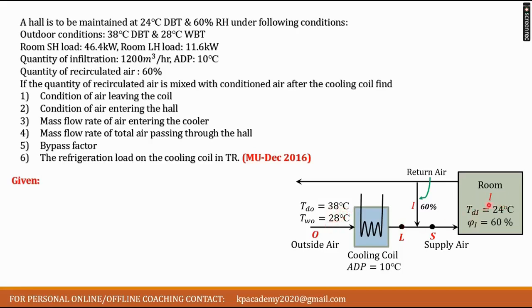Through some means we have room sensible heat and room latent heat given, that is 46.4 kilowatt and 11.6 kilowatt. But there is another thing that is given, the air infiltration. Through some means we have some air infiltrated into the room. The rate of that is 1200 meter cube per hour. We have the coil temperature given to us as 10 degrees Celsius, and the quantity of air recirculated. That means room air is again recirculated over here and it is 60%, right?